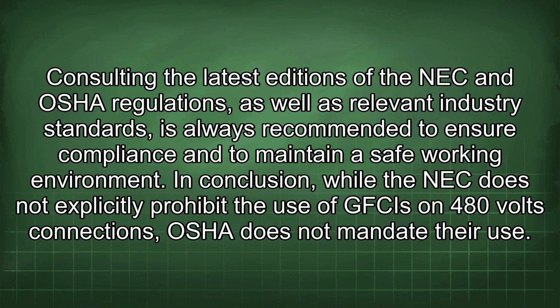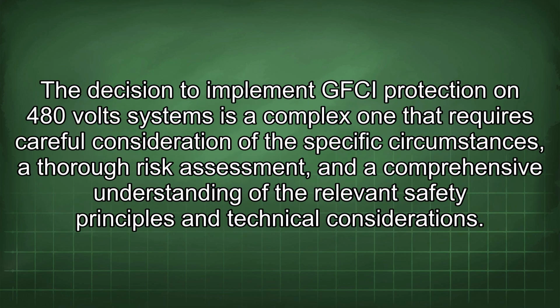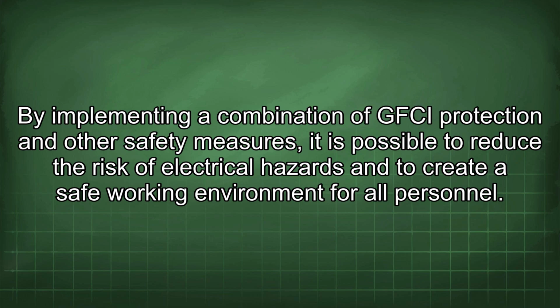In conclusion, while the NEC does not explicitly prohibit the use of GFCIs on 480 volts connections, OSHA does not mandate their use. The decision to implement GFCI protection on 480 volt systems is a complex one that requires careful consideration of the specific circumstances, a thorough risk assessment, and a comprehensive understanding of the relevant safety principles and technical considerations. By implementing a combination of GFCI protection and other safety measures, it is possible to reduce the risk of electrical hazards and to create a safe working environment for all personnel.